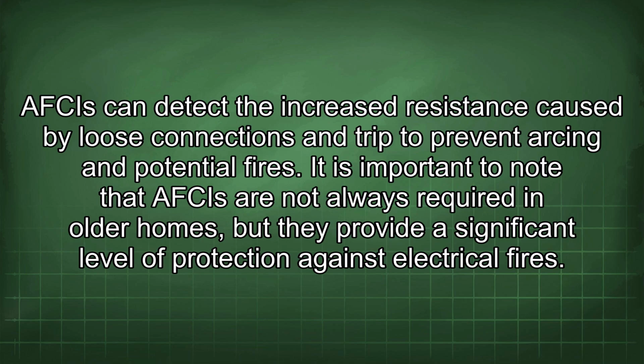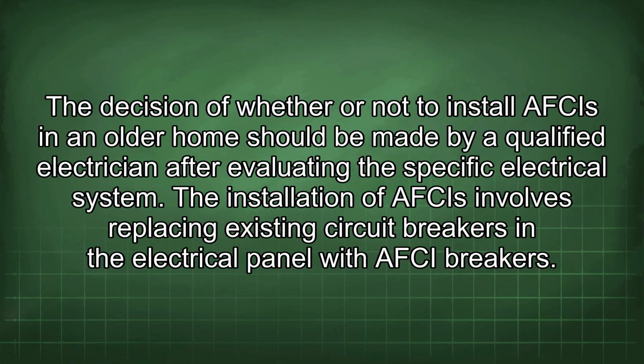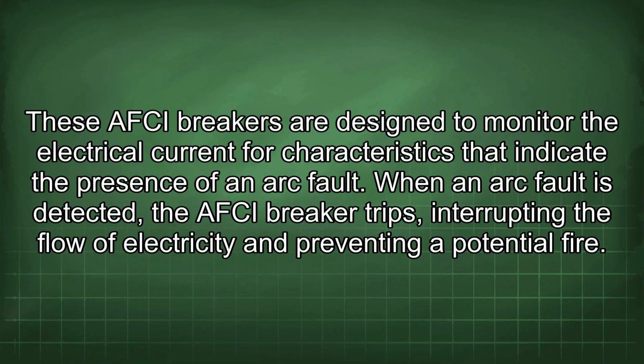It is important to note that AFCIs are not always required in older homes, but they provide a significant level of protection against electrical fires. The decision of whether or not to install AFCIs in an older home should be made by a qualified electrician after evaluating the specific electrical system. The installation of AFCIs involves replacing existing circuit breakers in the electrical panel with AFCI breakers. These AFCI breakers are designed to monitor the electrical current for characteristics that indicate the presence of an arc fault. When an arc fault is detected, the AFCI breaker trips, interrupting the flow of electricity and preventing a potential fire.